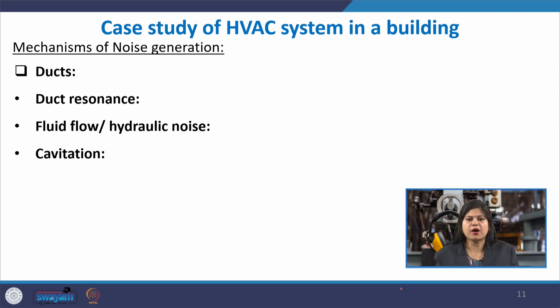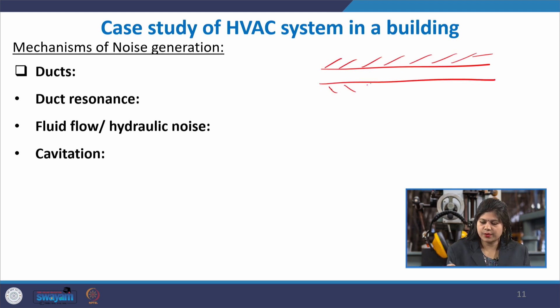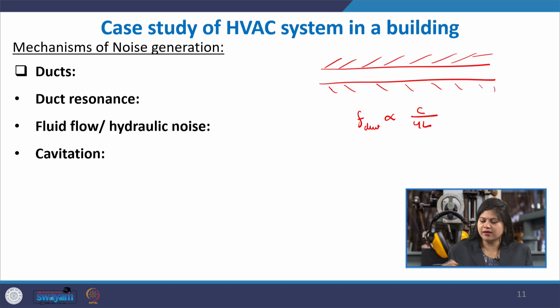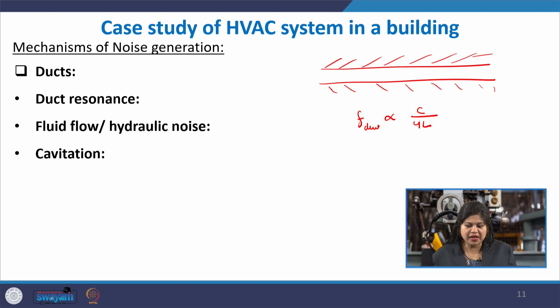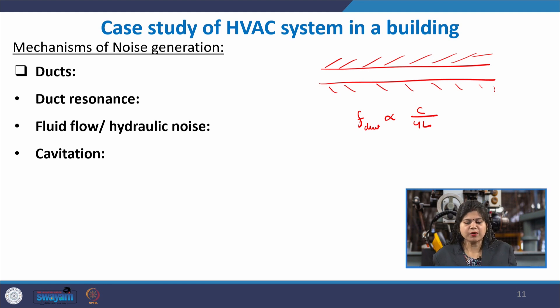Ducts are a major part of the HVAC system and act as confined acoustic cavities. The fundamental frequency of any duct is proportional to C/4L and depends on the duct geometry, primarily its length. When fluid or air flows through the ducts, the flow can excite the duct at its resonance frequency, producing sharp tonal sounds — making duct resonance a very common noise source in HVAC ducting.